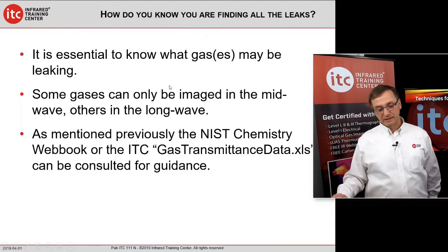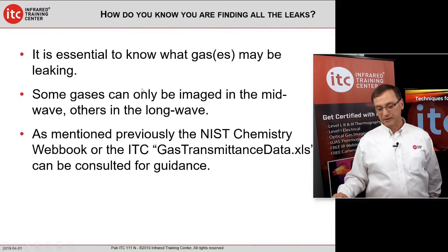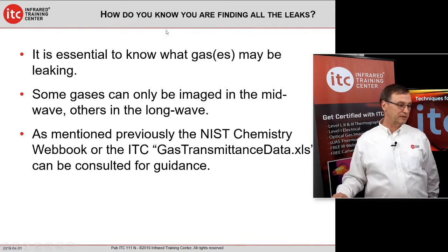Okay. And it's essential to know what gases are leaking, if any. If you're just looking for methane, ethane, propane, that's one thing. If you're in a refinery or a chemical plant and you have other gases, some may be very difficult to impossible to image. Some can only be imaged in the long wave, some in the mid wave.